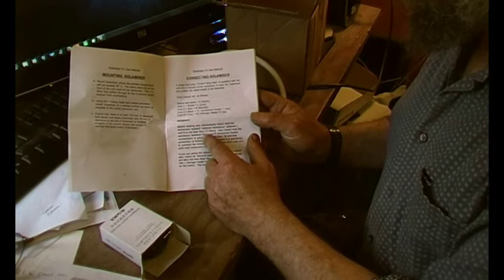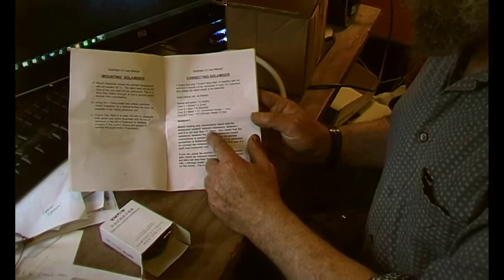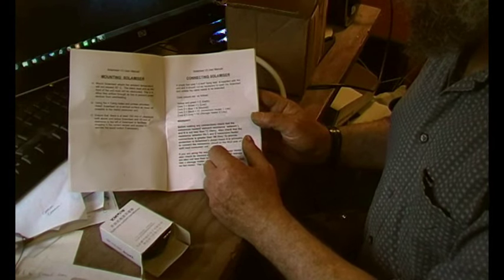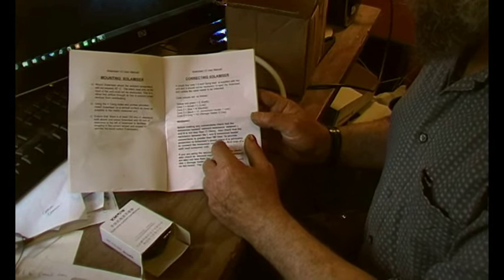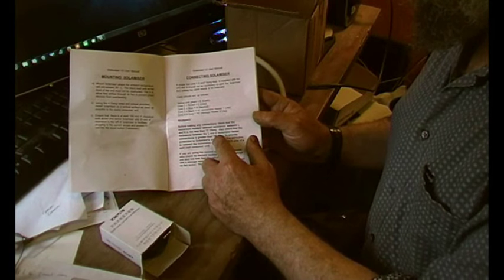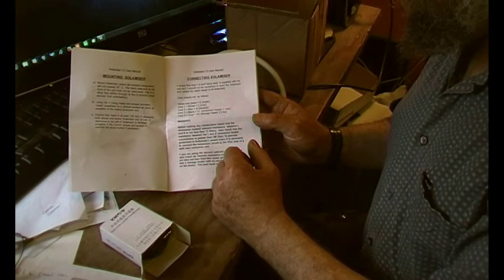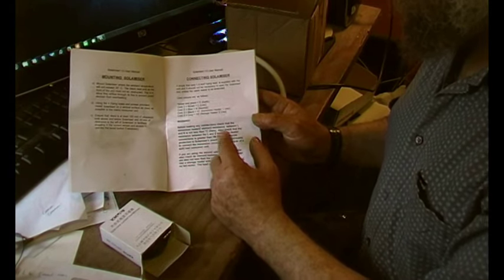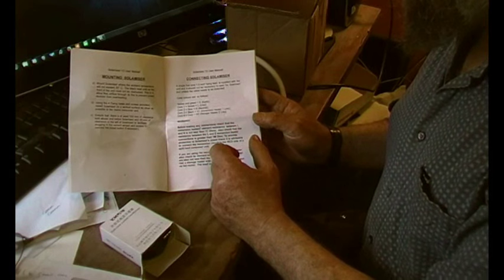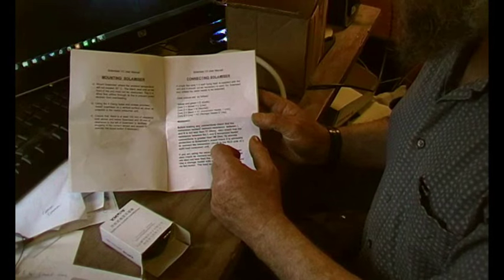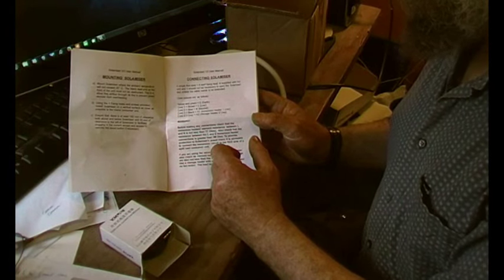And then you've got to have 17 ohms. And then also between live and earth, you have to check that it's greater than one mega ohm. So that just checks the quality of the circuit there.